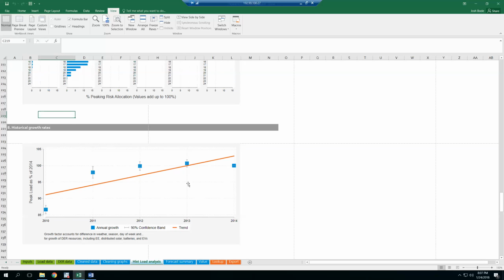The other factor that jumps out for me when I look at this is the amount of variability around the trend line. If there's a lot of variability, which typically happens with smaller locations where changes in load are more disruptive, the variability is going to have a big influence on the load in the forecast, because the more variability we have in growth, the less we know what growth will be like 5-10 years from now.